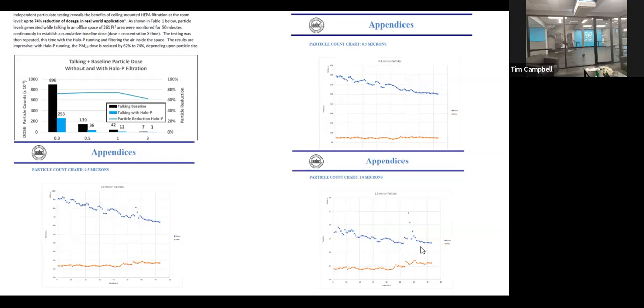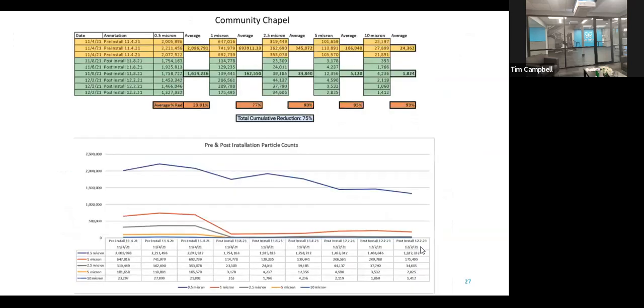So we worked, meaning we placed the halos as close to the return vents. So as the air was already being pulled up from their existing HVAC system, the halo was working with it to capture any of the particles present in that facility. So the baseline we got before installation is the blue graph, and then the baseline after installation is the orange line. And what we saw was an average reduction of 80% between particles 0.3 up to 1 micron in size. Massive reduction.